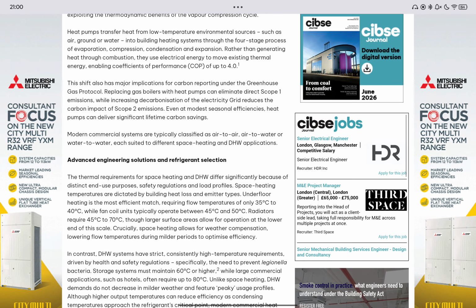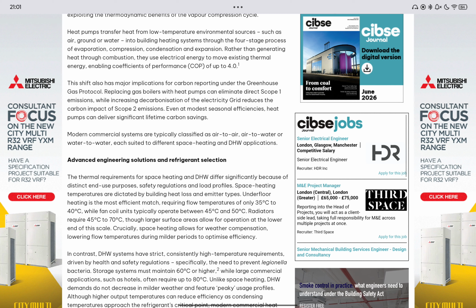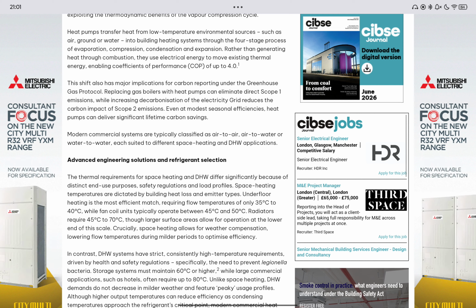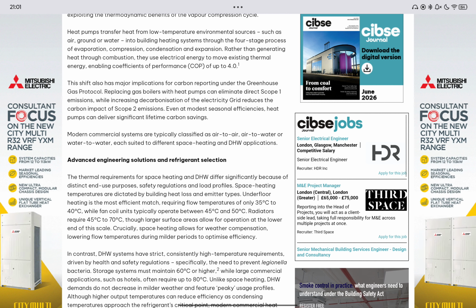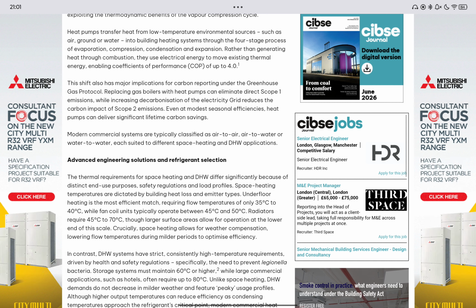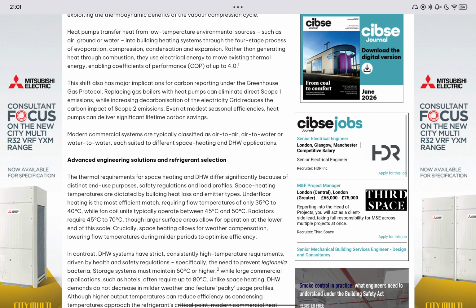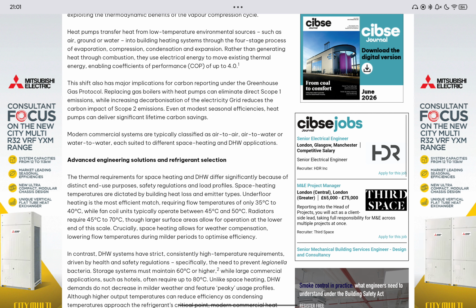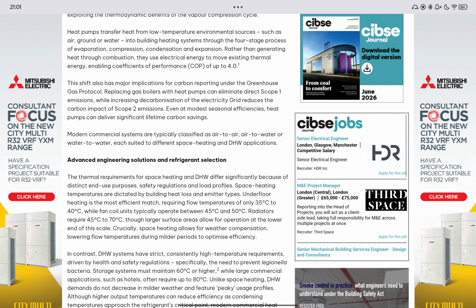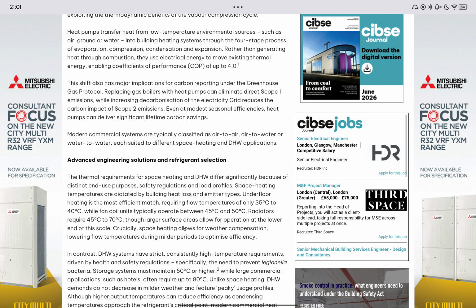This shift also has major implications for carbon reporting under the Greenhouse Gas Protocol. Replacing gas boilers with heat pumps can eliminate direct Scope 1 emissions, while increasing decarbonisation of the grid reduces the carbon impact of Scope 2 emissions. Even at modest seasonal efficiencies, heat pumps can deliver significant lifetime carbon savings. Modern commercial systems are typically classified as air-to-air, air-to-water or water-to-water, each suited to different space heating and DHW applications.